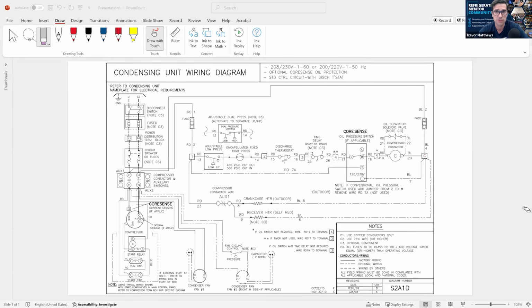So this technician was showing that the disconnect was off. He was still getting 450 or 460 volts across that system when the main disconnect was off. So you want to use ground for safety. And you want to always go across. So the example that we're going to use today is a 208, 230 single phase 60 hertz. So if you're listening, try to follow along.